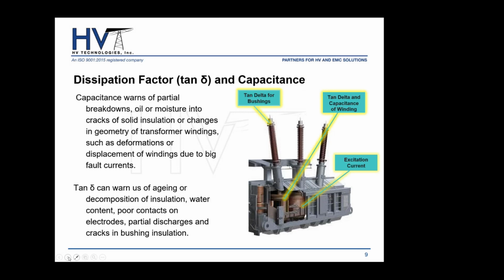Basically, when we test for dissipation factor and capacitance, we get the following information from these tests. Capacitance will warn us of partial breakdowns, oil or moisture that can be seeping into the cracks of solid insulation, or it could also warn us of changes in the geometry of a transformer winding. For example, if a transformer experiences a short circuit or a huge fault current, and there has been a shifting of windings or a deformation to some of the windings, it could also warn of those changes.